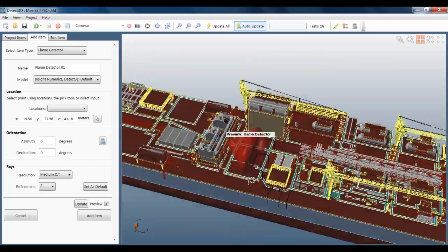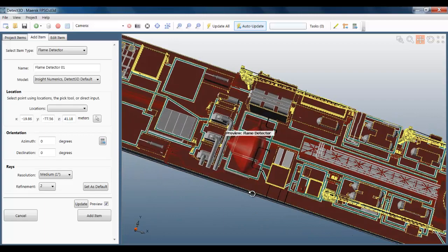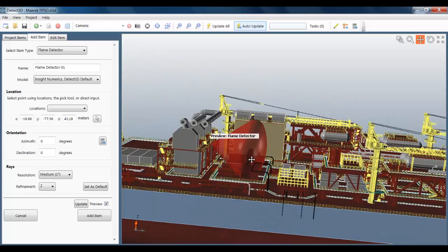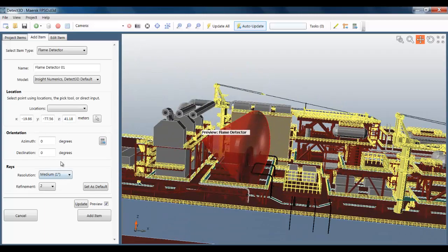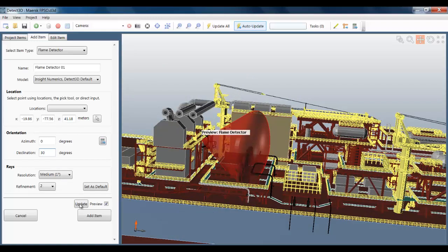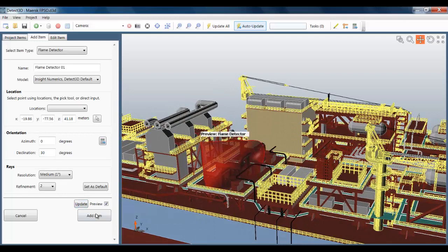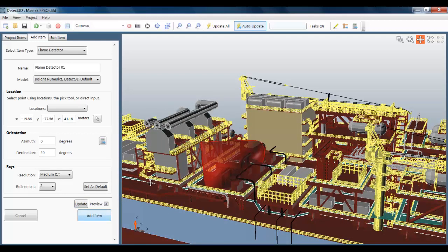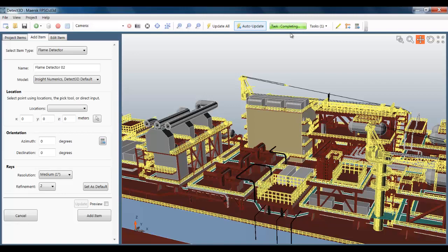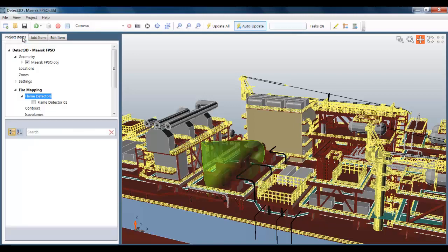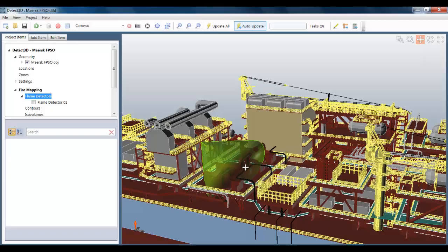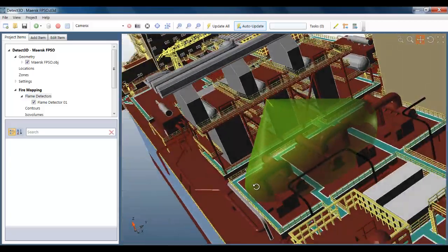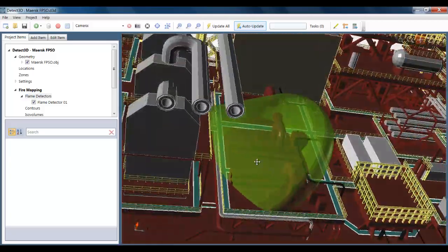You can see that the azimuth is about right. But I'm going to angle it down by about 30 degrees, which is fairly typical for a detector. And I'm going to add that now to the project. Now this bar at the top indicates the progress of the current calculation, which is the raycasting algorithm to calculate the obstructed field of view for the detector I just added. There's no doubt that it took a few seconds rather than a few tenths of seconds. But that's just a function of the larger model that I'm looking at.